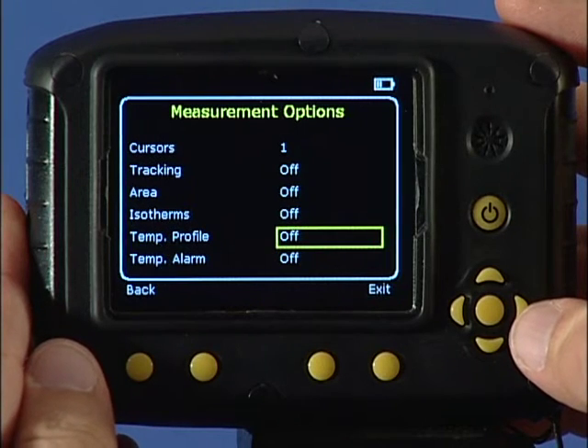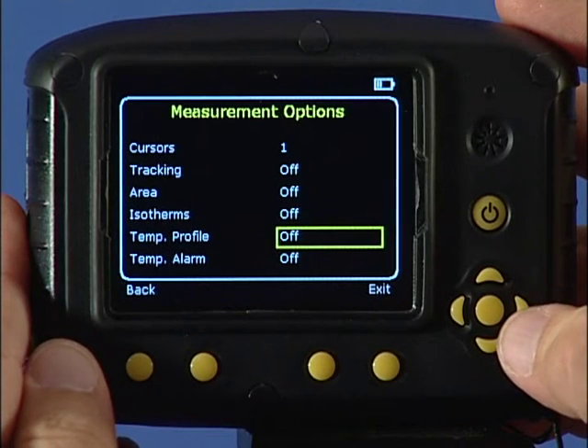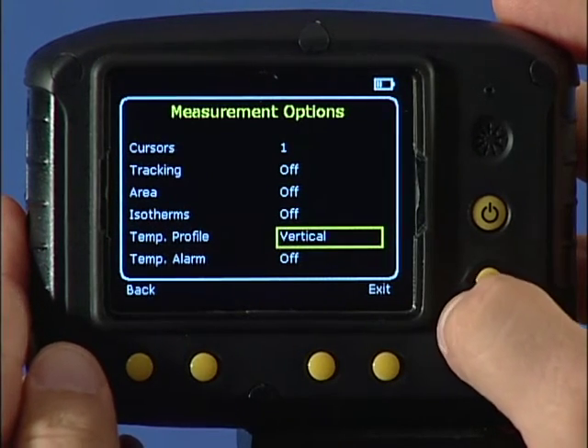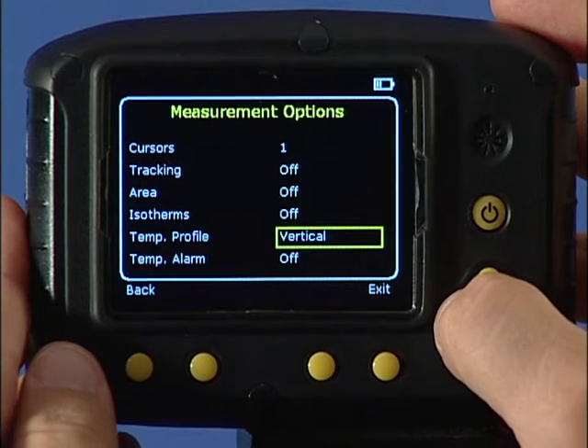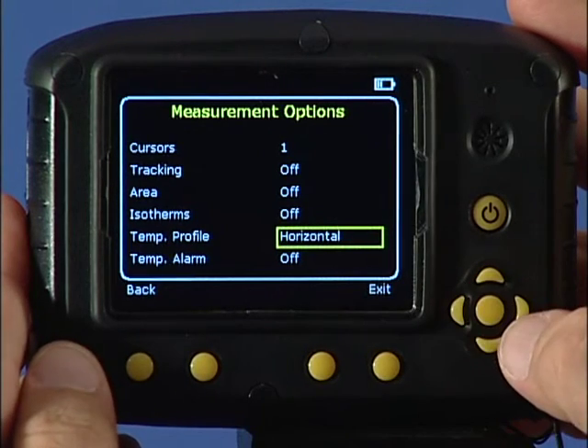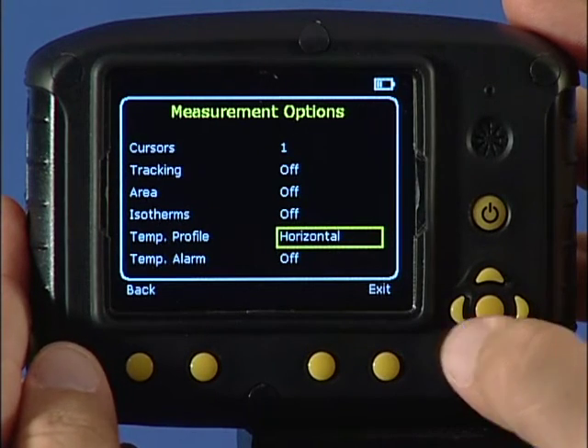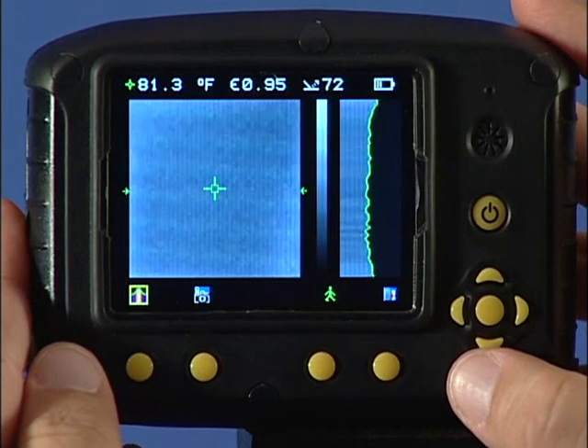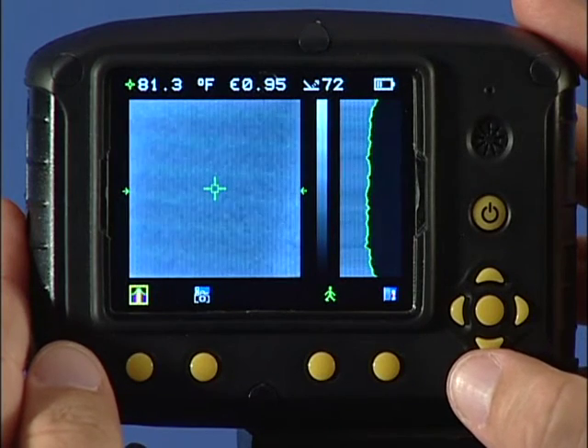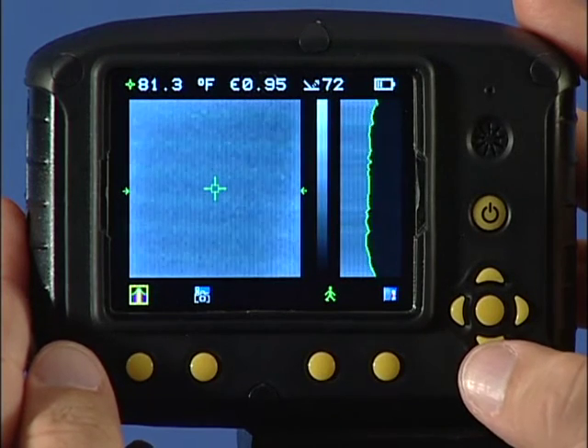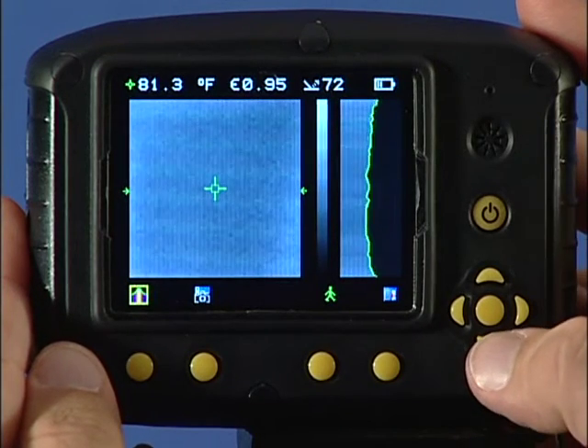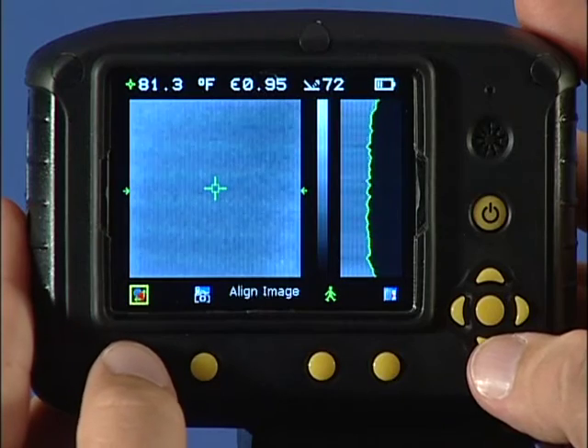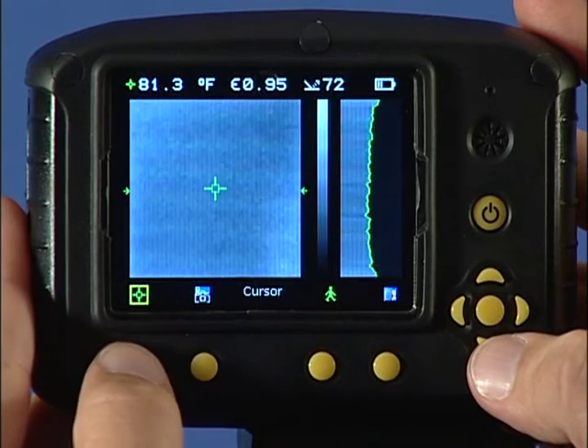The temperature profile function enables a vertical or horizontal histogram of temperature values across the imaged area to be displayed on the right-hand side of the screen. The position of the cross-section is indicated by the small arrows and can be adjusted using function key 1 and the navigation keys.